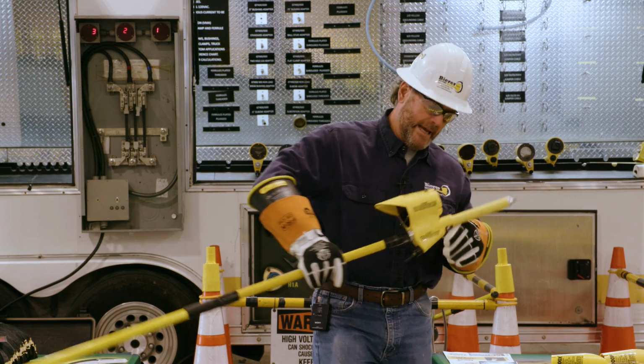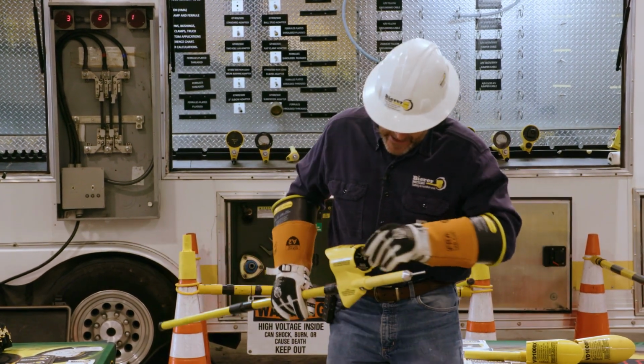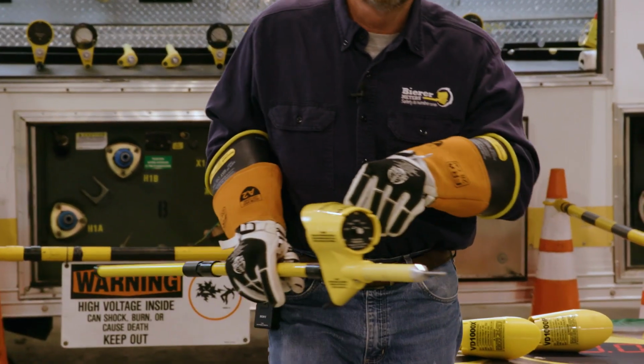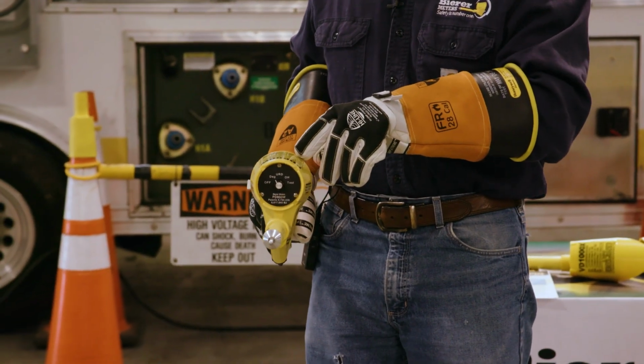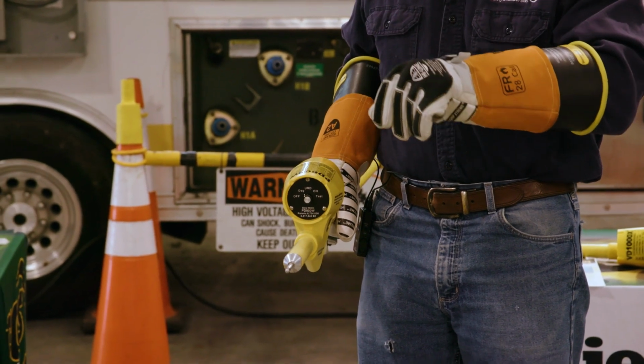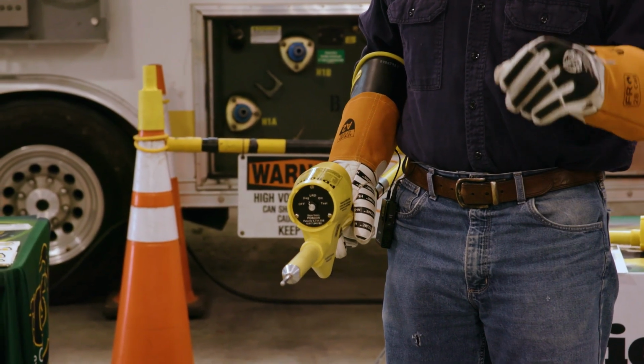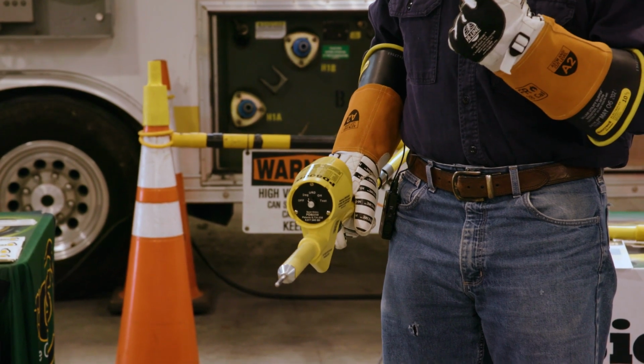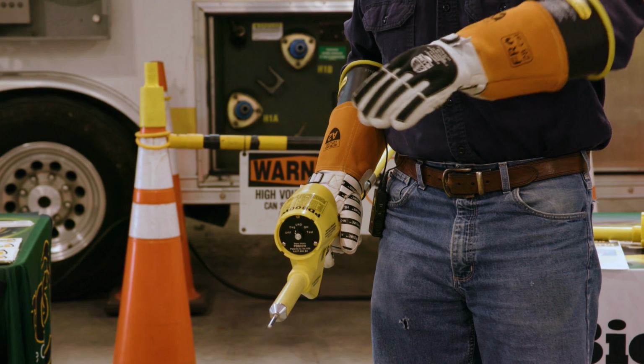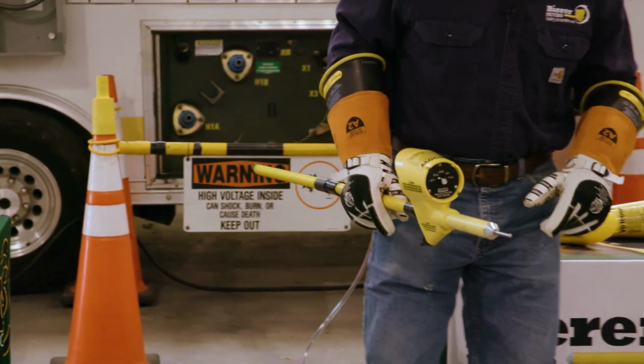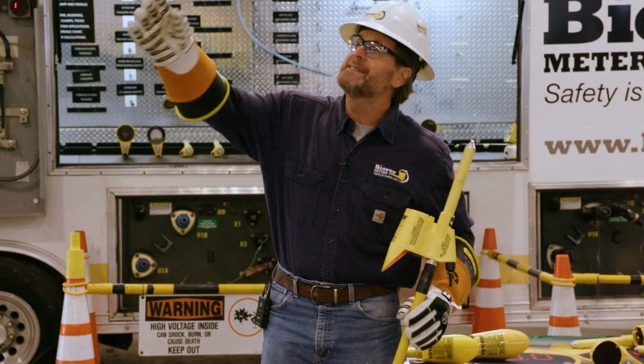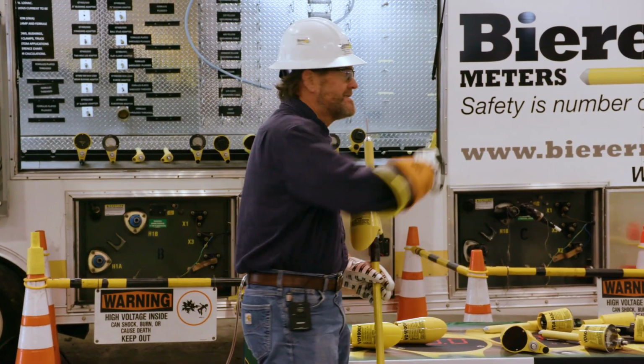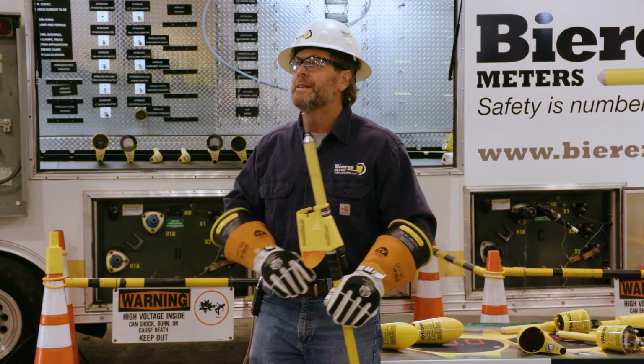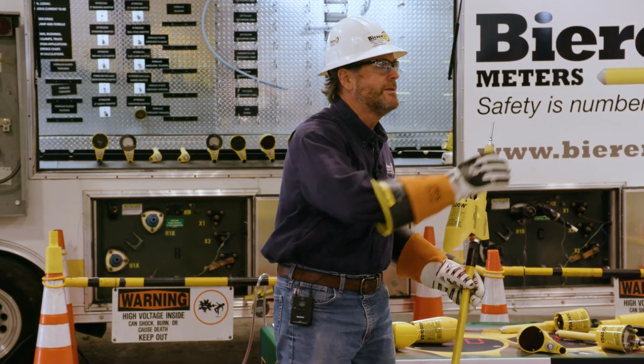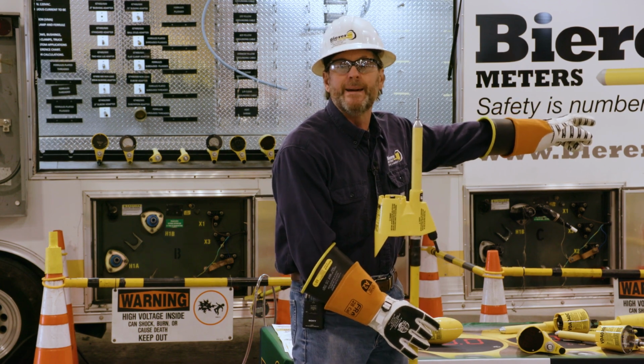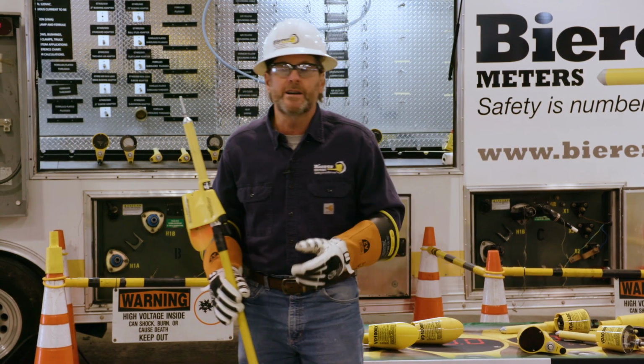So your tool has a switch plate with degrees. When you take your PD800W and put it in degrees, that's when you're using it for phasing. It's going to look at the phase angle. In degrees, it doesn't care about potential, whether you're on the high side, low side, transmission side, secondary side, underground, or overhead. It only cares about the phase angle the generation plant is making. Three phase, that's all it cares about.